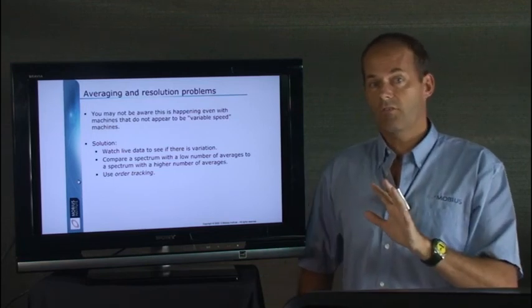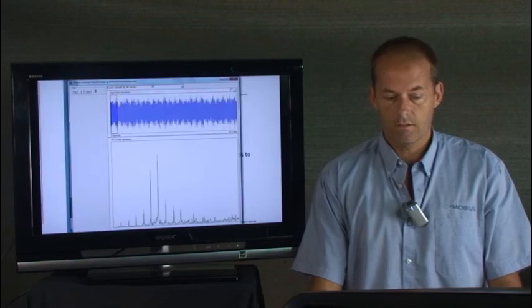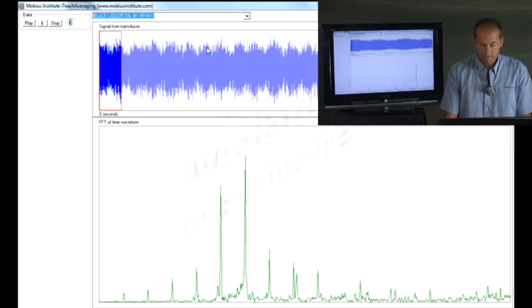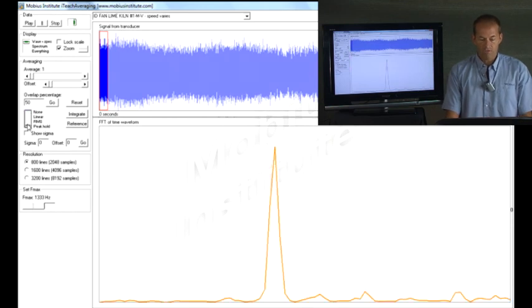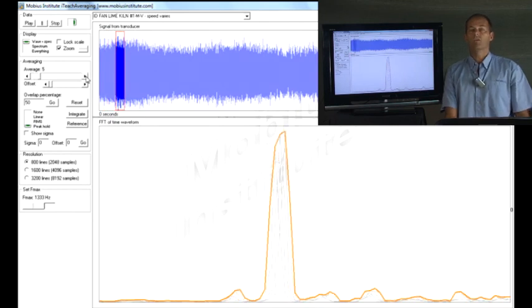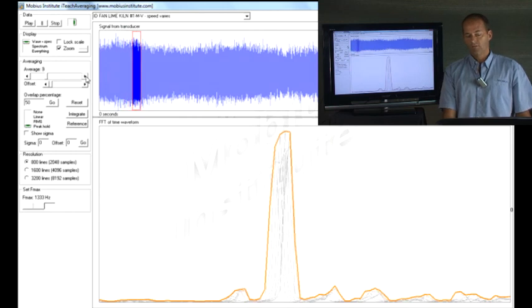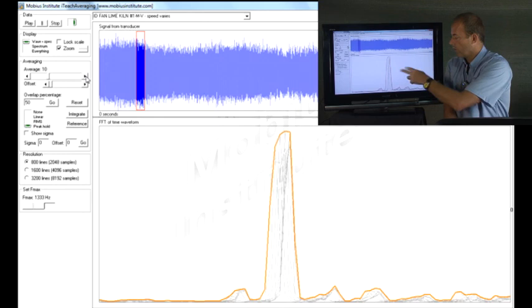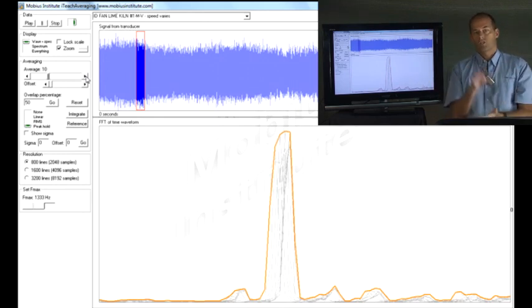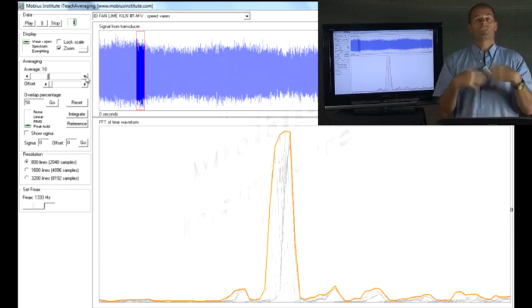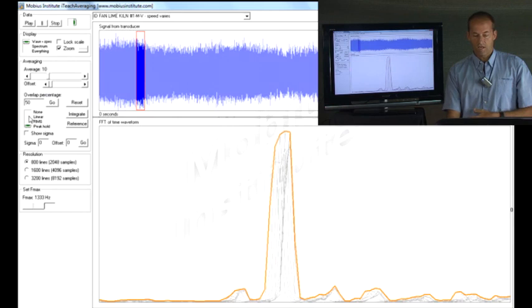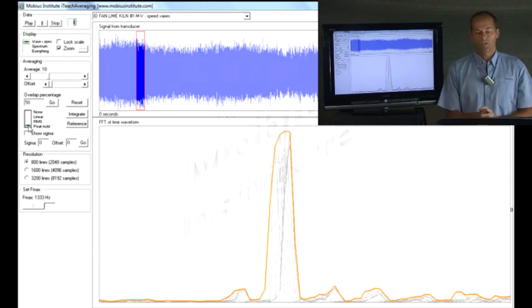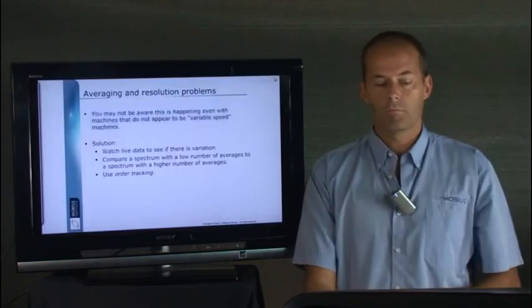One option is to use peak hold averaging. Just watch this for a second. If I just bring this up again and we look at this vibration and we zoom in and I turn on peak hold average and I go through my averaging process. What it's doing now is it's keeping all of the vibration during that variation. And notice I get a much more distinct view of how the vibration changed. Now, in theory with the normal machine, your peak hold average and your normal average shouldn't vary by so much unless there's a lot of noise. Well, here this would be a demonstration. That's using peak hold average. That's using linear average. You see there's quite a difference between that and that. So you can do that in your machine. So it's just something, with your more important machines or if you suspect a problem, that's something you can do.